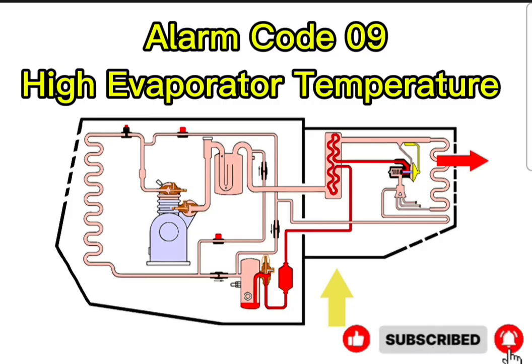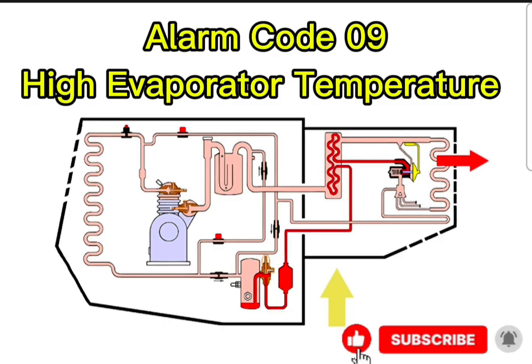But as we wrap up this deep dive, there is one final lingering thought I want you to mull over. It goes all the way back to that strict, bolded rule we mentioned right at the very beginning of the deep dive. Yes. The manual states, this alarm is cleared manually. The absolute demand for a human being. Right. Think about the incredible, overwhelming sophistication of this refrigeration system. It has service watch data loggers that record environmental telematics down to the millisecond. It has complex physical arrays of electromechanical solenoids and dampers. It has multiple redundant layers of sensors constantly talking to a central microprocessor. And yet, when the true crisis hits, when it crosses that 155-degree threshold, this entire automated marvel intentionally paralyzes itself. It throws its hands up, locks the doors, and demands a human hand to reset the switch. It recognizes the limits of its own logic.